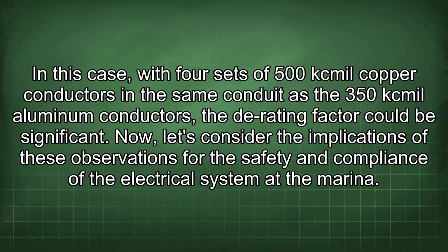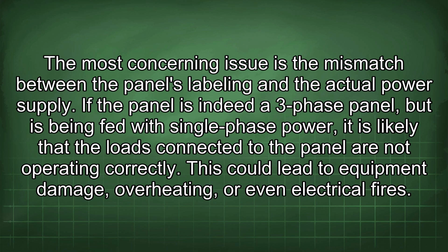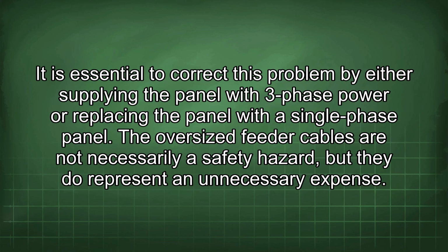Now, let's consider the implications of these observations for the safety and compliance of the electrical system at the marina. The most concerning issue is the mismatch between the panel's labeling and the actual power supply. If the panel is indeed a three-phase panel, but is being fed with single-phase power, it is likely that the loads connected to the panel are not operating correctly. This could lead to equipment damage, overheating, or even electrical fires. It is essential to correct this problem by either supplying the panel with three-phase power or replacing the panel with a single-phase panel. The oversized feeder cables are not necessarily a safety hazard, but they do represent an unnecessary expense.